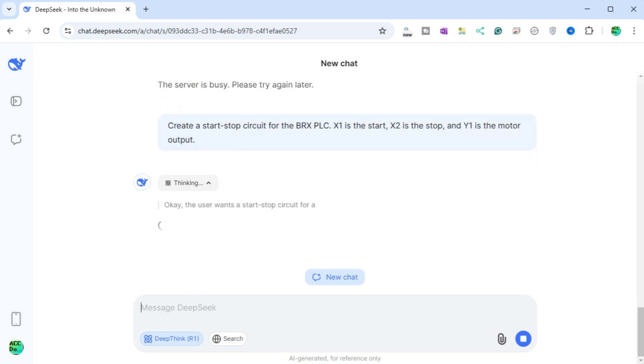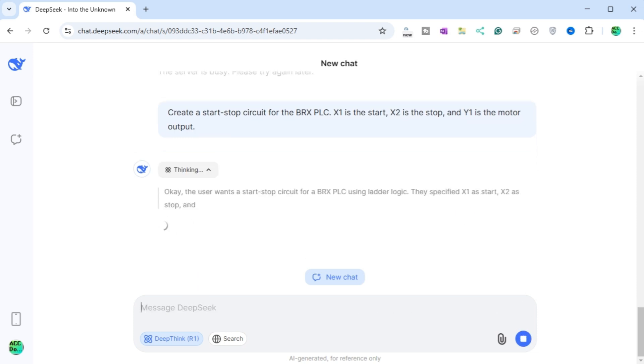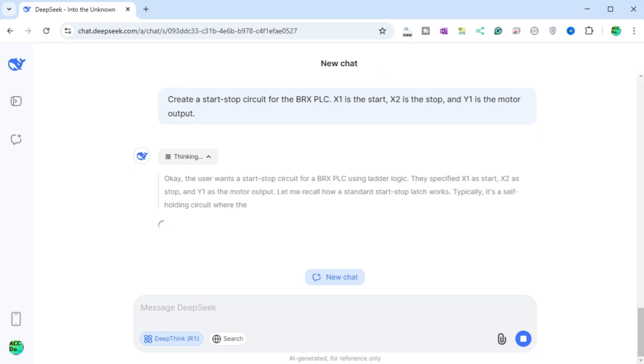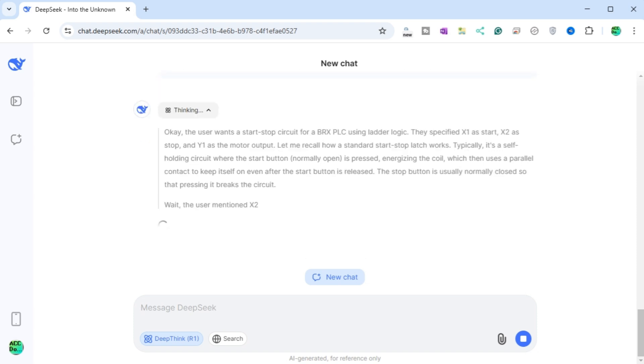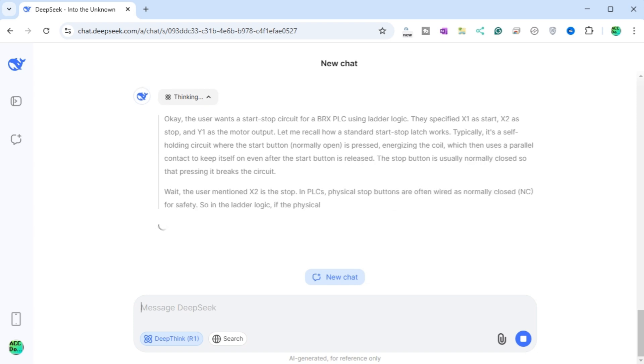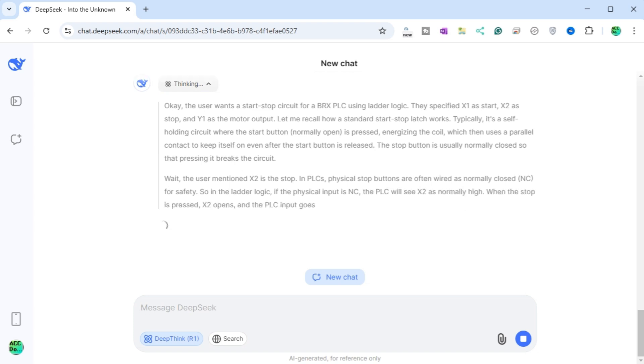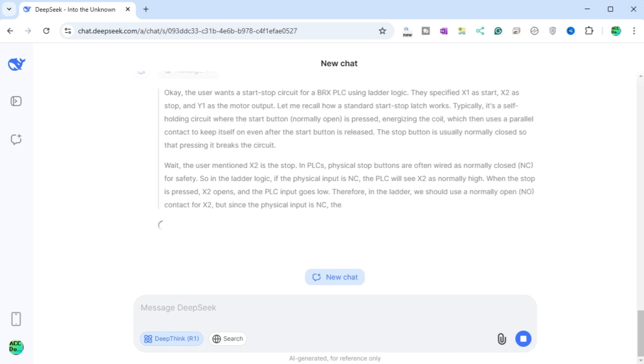DeepSeek's reasoning: The user wants a start-stop circuit for a BRX PLC using ladder logic, with X1 as start, X2 as stop, and Y1 as motor output. In a standard start-stop latch, the start button (normally open) is pressed to energize the coil, which then uses a parallel contact to keep itself on even after the start button is released. The stop button is usually normally closed, so pressing it breaks the circuit. Since the physical stop button is wired NC, the PLC will see X2 as normally high — when the stop is pressed, X2 opens and the PLC input goes low. Therefore, in the ladder we should use a normally open (NO) contact for X2.